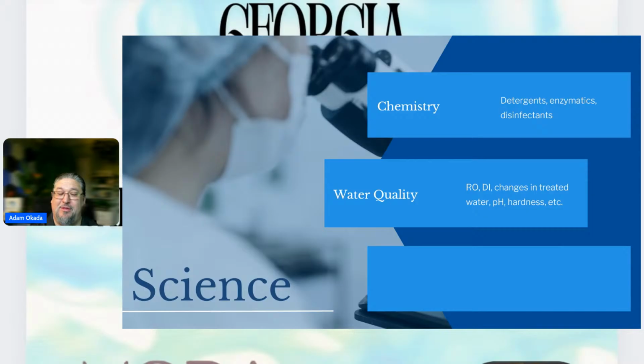pH can affect your water, and so can the hardness. I've done a little bit of digging into the hospitals that are in the news. Whenever I see a hospital that got shut down by the state, where they stopped surgeries at the facility because SPD was having issues, I've been looking into this more closely, and almost every single one has issues with water quality. It's really a thing that can get you shut down.